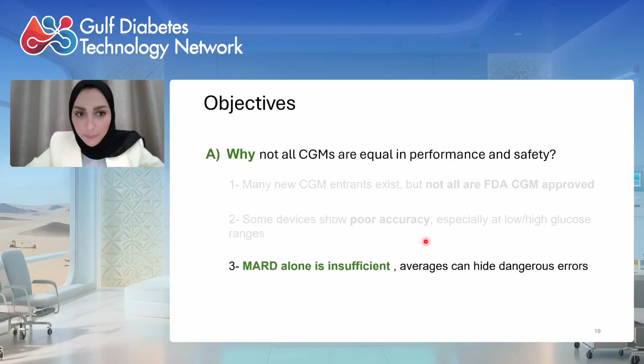It will give you an average overview of the difference between the sensor glucose reading and the blood glucose reading. So basically, for the people who don't know, it is a way of testing the accuracy of the sensor. It will show you how much difference there is between blood glucose or plasma glucose and sensor glucose. So the lower the MARD, the better the accuracy, roughly. So we always say if the MARD is lower, it means that there is less difference between the plasma glucose and the sensor glucose reading.